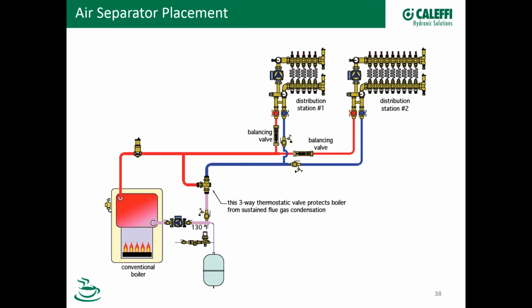Another picture just for variety. Here's a conventional boiler, so we show the air separator right on the outlet, and this is a boiler protection valve, so that's for here. But what I wanted to show too is, remember, here's some high points out here. So our manifolds will want to have air vents out on any high point location out there too.